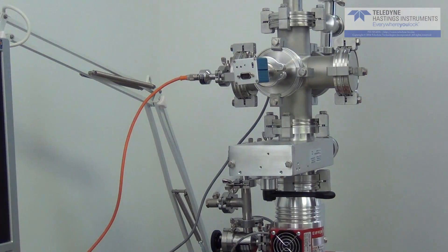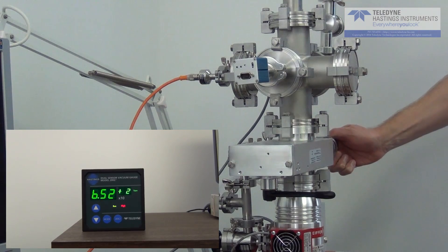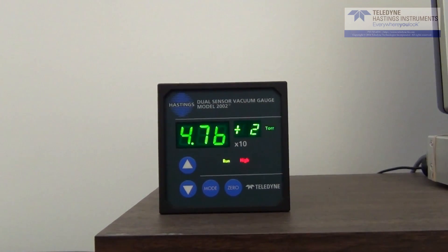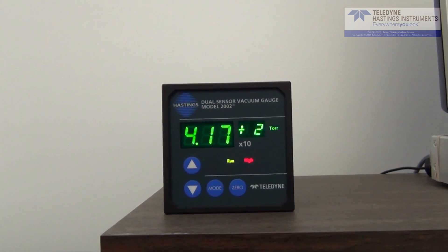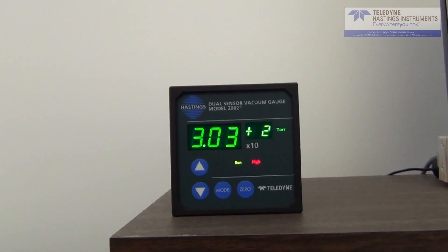Now let's see the HPM 2002 in action. I've got a gauge tube hooked up to the system over here, and I'm going to begin to rough it out. So you'll hear the pump start to kick in here. And remember, the microprocessor is looking at only the piezoresistive sensor above 32 torr.